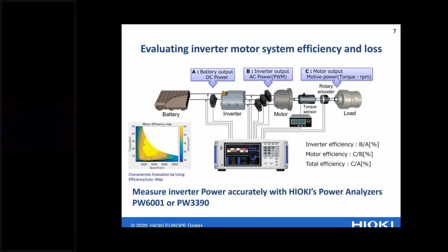As an example, we have a power analyzer, the PW6001, a 6-channel module which you can use as master-slave. Ideally you can set up to 12 channels, which gives you the ability to check before and after the inverter, for instance, what comes in and what goes out, to get an understanding of the real efficiency of your drive system.